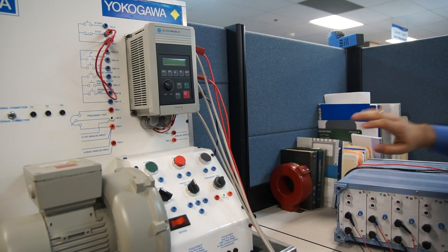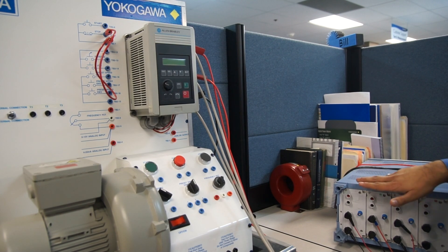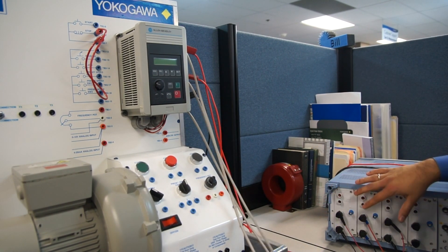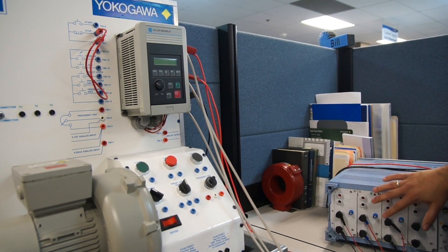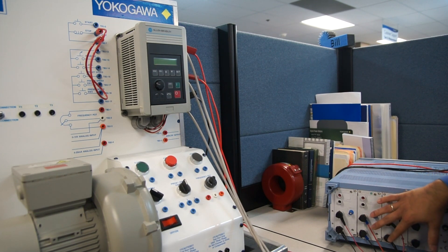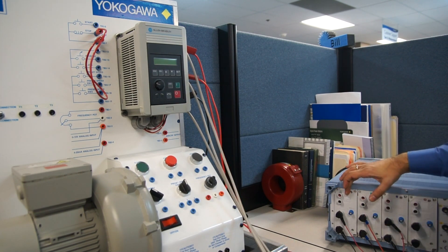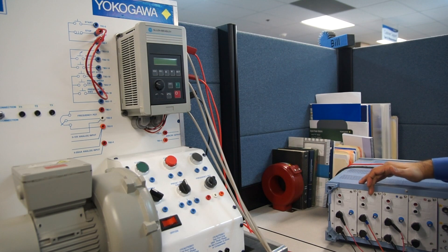I have pre-wired my currents to the power analyzer with phase A positive and negative, phase B positive and negative, and phase C positive and negative. You can see that I have wired phase A to wattmeter one, phase B to wattmeter two, and phase C to wattmeter three.